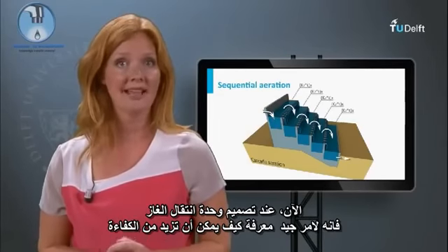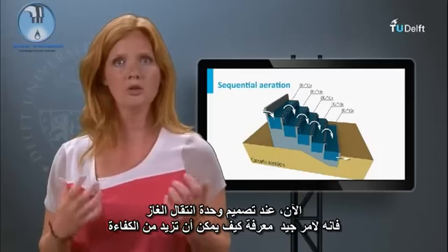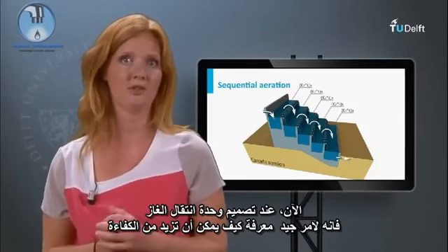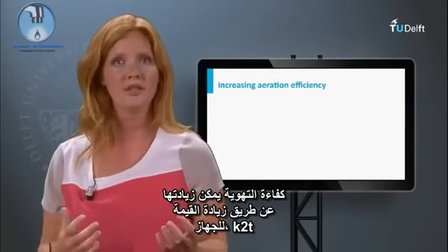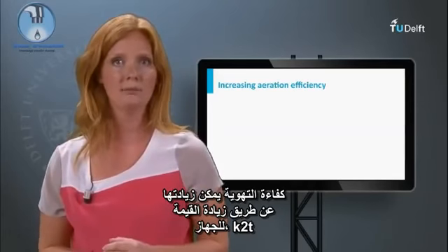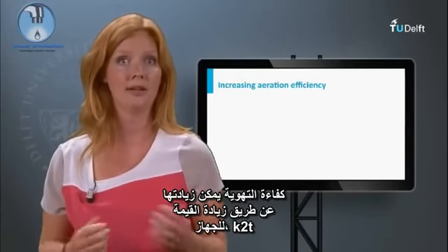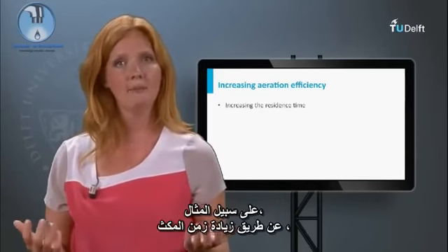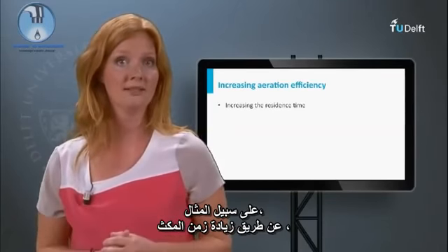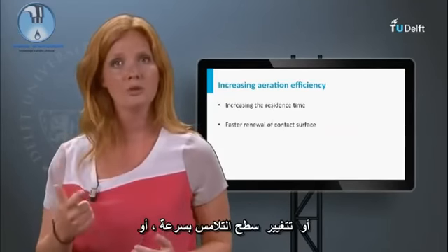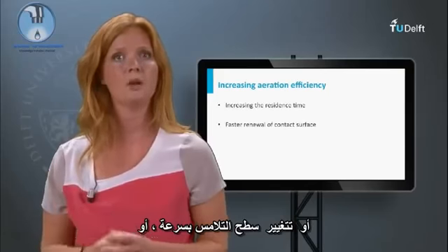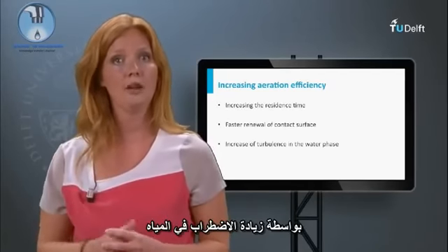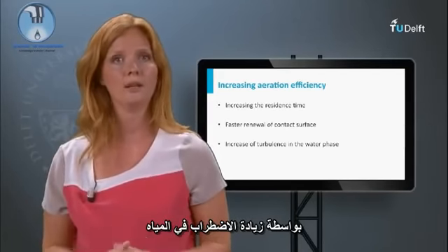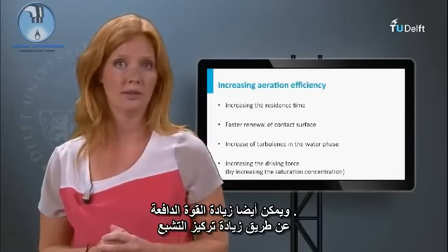Now, when designing a gas transfer installation, it is good to know how you can increase the efficiency. The efficiency of aeration can be increased by increasing the K2T value of the device. For example, by increasing the residence time, by faster renewal of contact surface, or by increasing of turbulence in the water phase.